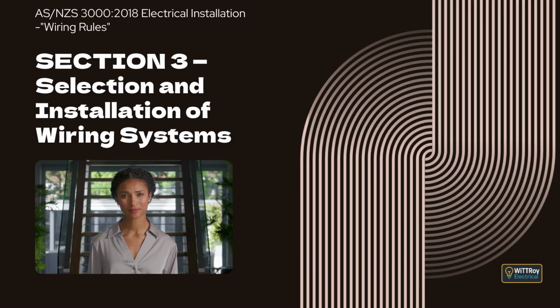Clause 3.16. Earth sheath return (ESR) system. This clause explains that an earth sheath return system is a system where the copper sheath of a MIMS cable acts as a single conductor that performs two functions at the same time, being both the protective earthing conductor and the neutral conductor. Only a copper sheath is permitted to be used in this combined role, and it is referred to as a PEN conductor. These cables must be installed in accordance with Clause 3.9.7.3, along with the additional conditions set out in this clause.